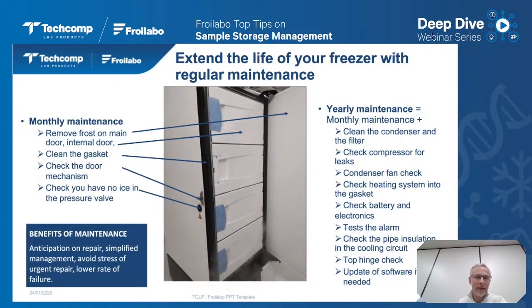The monthly maintenance is done by the users. They need to remove the frost on the main door and on the internal door. We supplied a tool to do it with the equipment. They will clean the gasket. They will check the door mechanism, because plenty of people can use the same equipment, and sometimes it's important to check whether the door mechanism is working well or not, and to check if we have ice in the pressure valve. It's very important. Also, it's easy to do. A monthly check is sufficient, and they can manage it themselves.